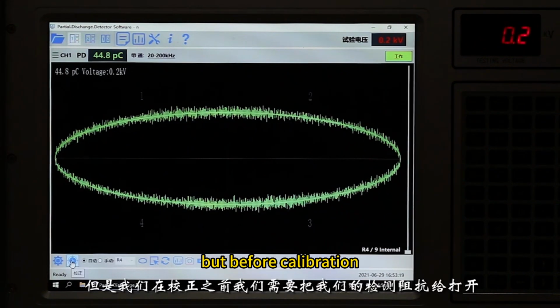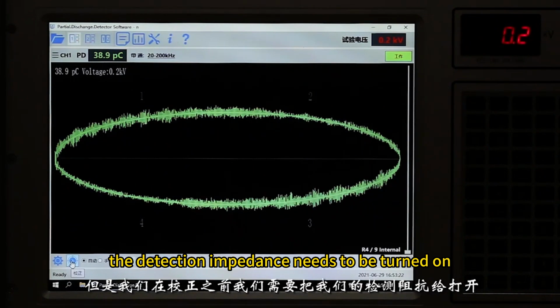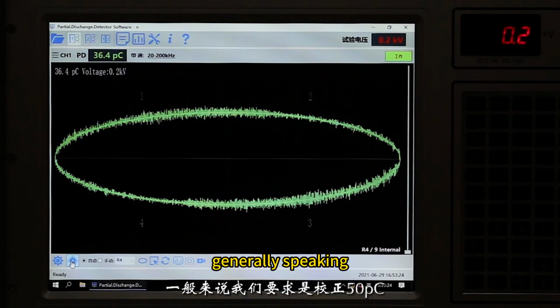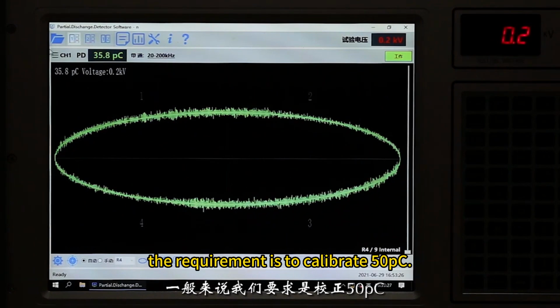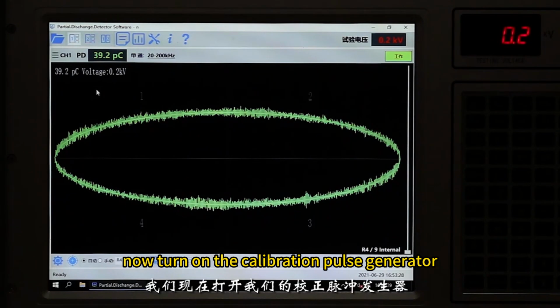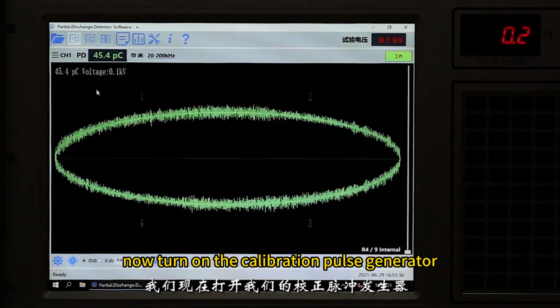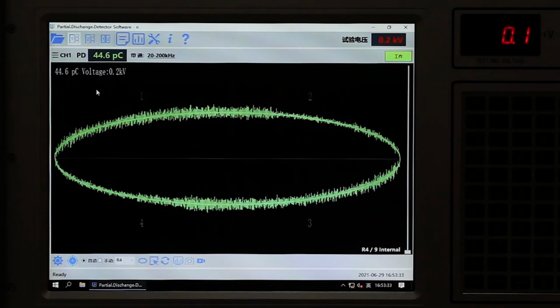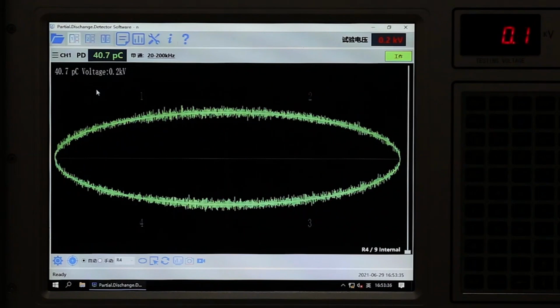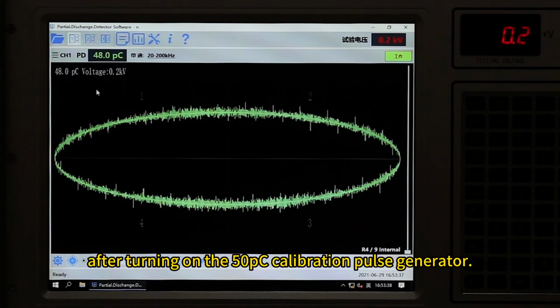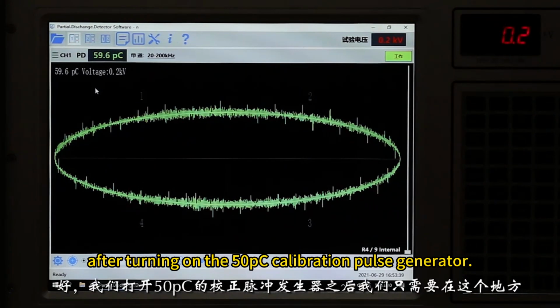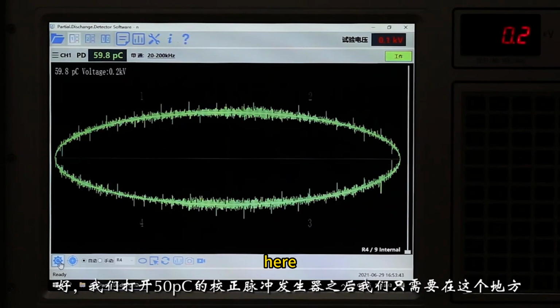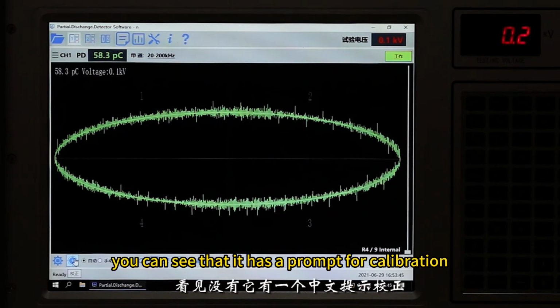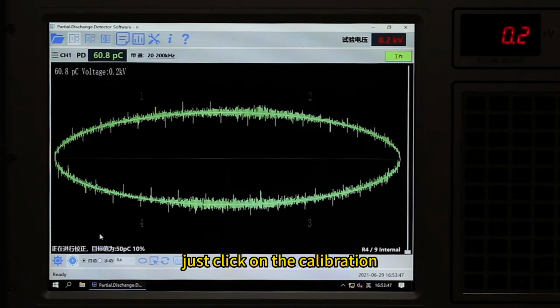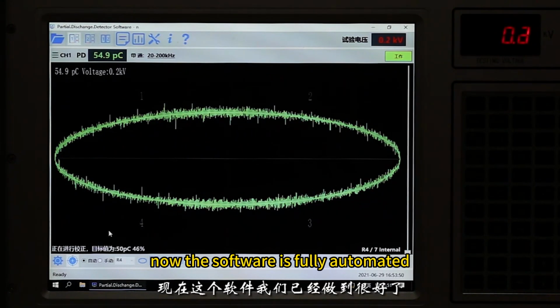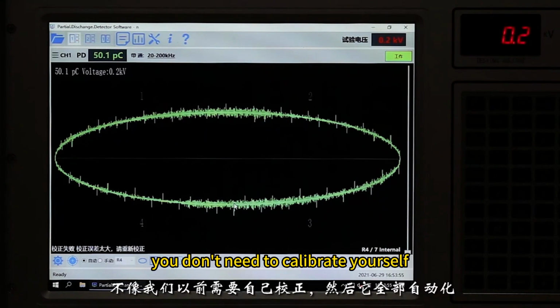But before calibration, the detection impedance needs to be turned on. Generally speaking, the requirement is to calibrate 50 PC. Now turn on the calibration pulse generator. After turning on the 50 PC calibration pulse generator, here, you can see that it has a prompt for calibration. Just click on the calibration. Now the software is fully automated. You don't need to calibrate yourself.